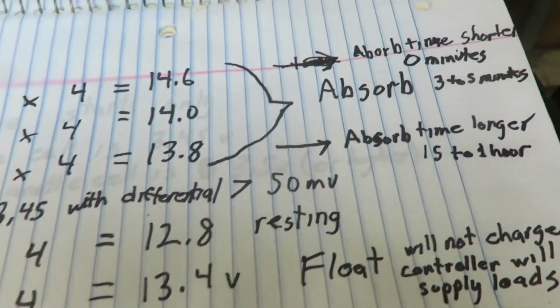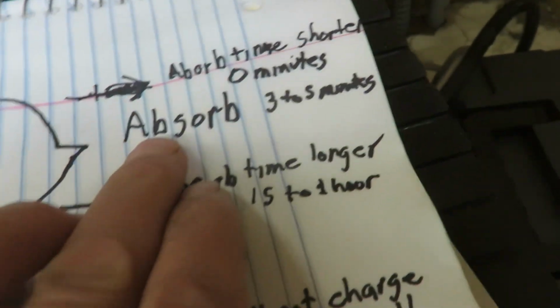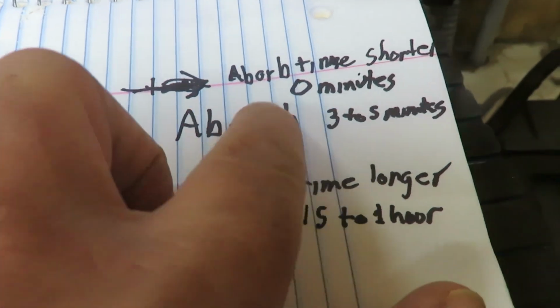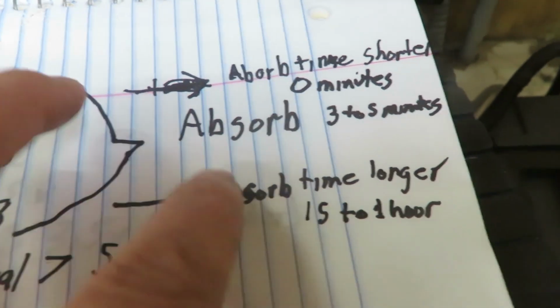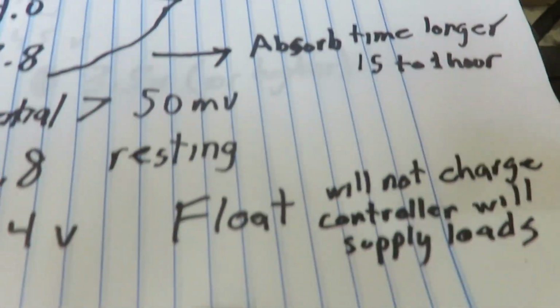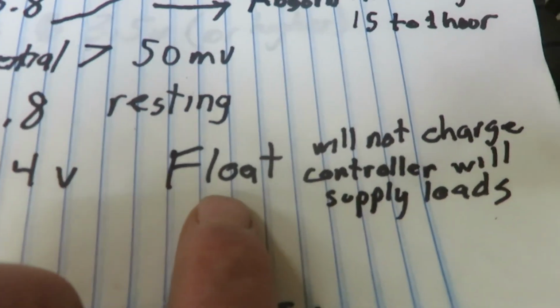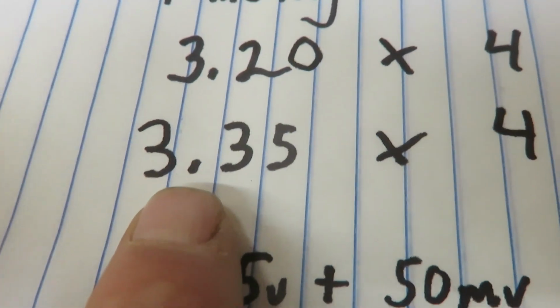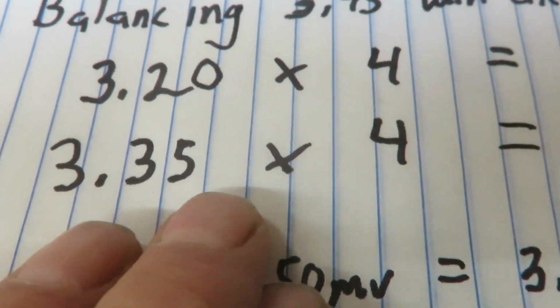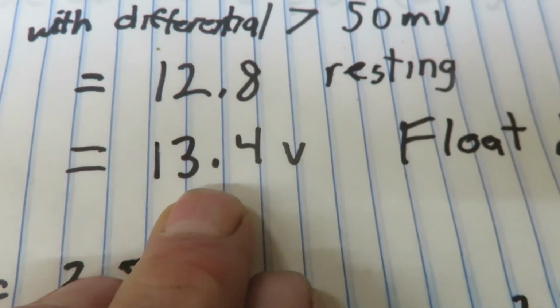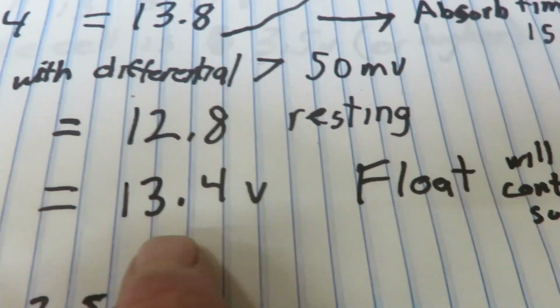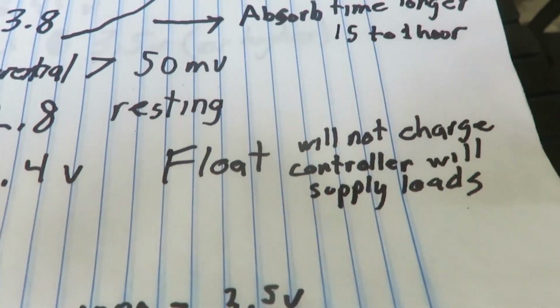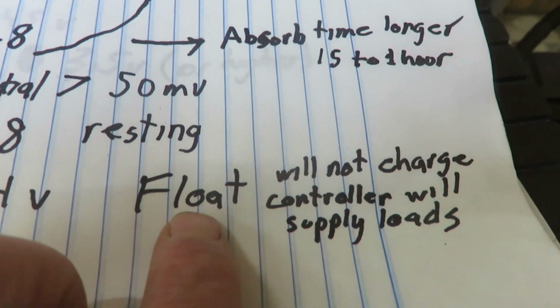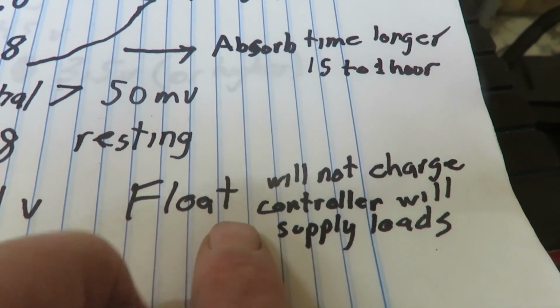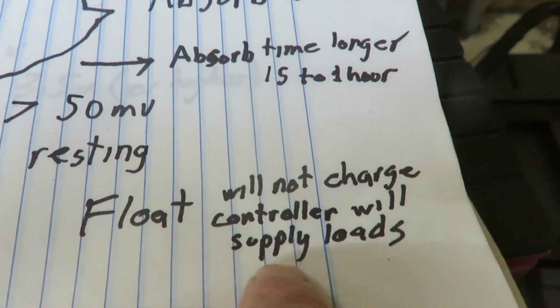So you've got your absorb setting, which is where it gets to the top, and when it's done absorbing, whether that's 0 minutes or 3 minutes or whatever you have it set for, you want it to go to float. Most controllers have a float. The float voltage is usually like 3.35 volts per cell times 4, which equals 13.4 volts. That's where I'd set the float, because at float it's basically not going to charge the cells anymore, but the controller will still provide all the loads.